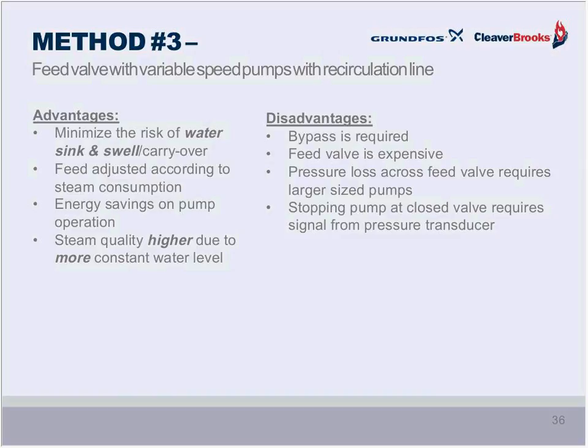Okay, advantages, disadvantages: that swell and carryover is minimized. There's some savings on pump operation, and the steam quality, again, can be higher than some of the other control methods. But on the disadvantage side, there's a bypass and the feed valve. We've mentioned those both chew up energy.